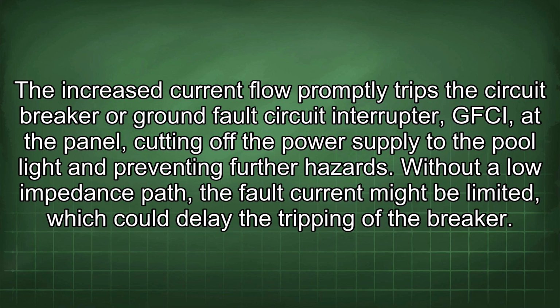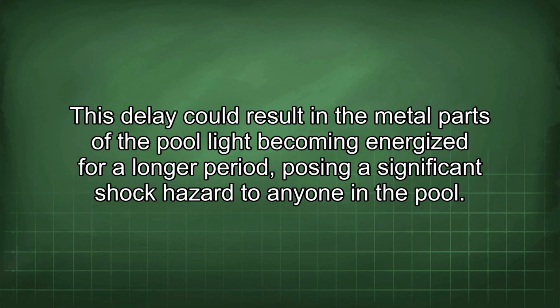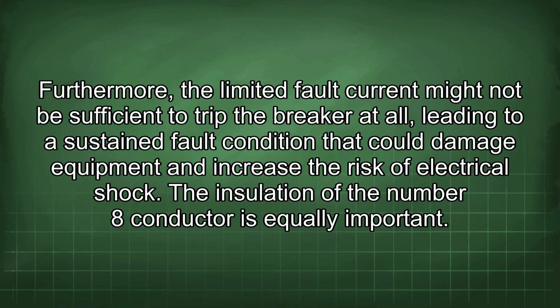Without a low impedance path, the fault current might be limited, which could delay the tripping of the breaker. This delay could result in the metal parts of the pool light becoming energized for a longer period, posing a significant shock hazard to anyone in the pool. Furthermore, the limited fault current might not be sufficient to trip the breaker at all, leading to a sustained fault condition that could damage equipment and increase the risk of electrical shock.